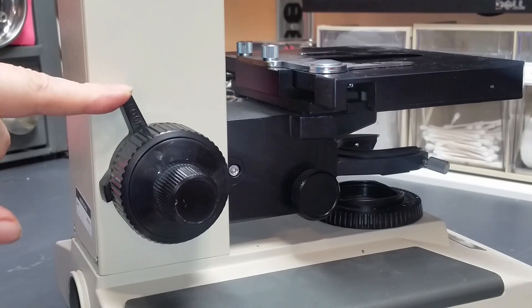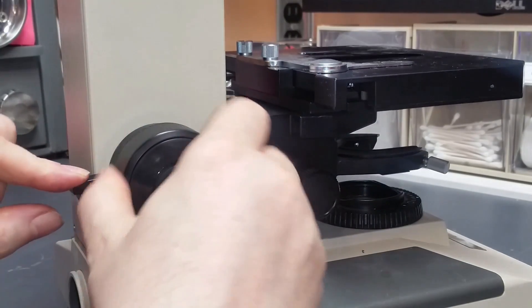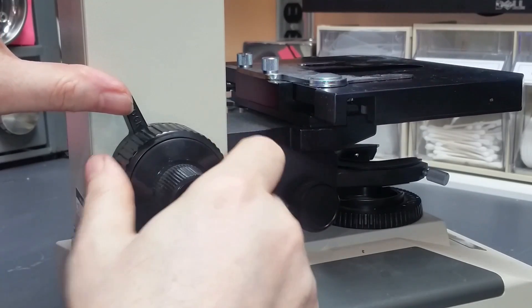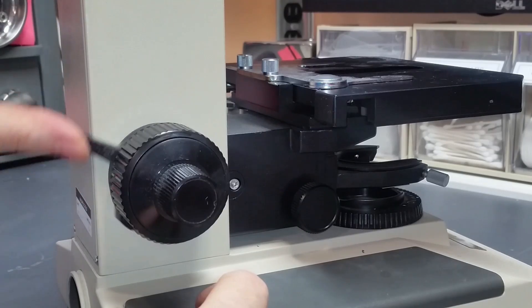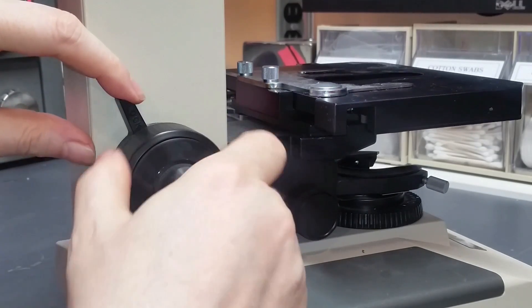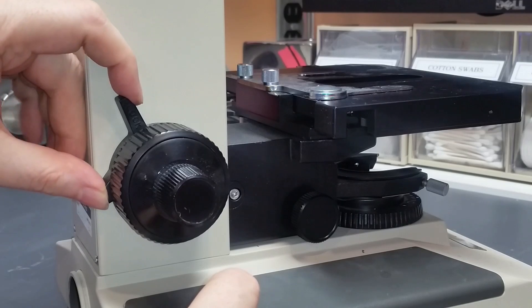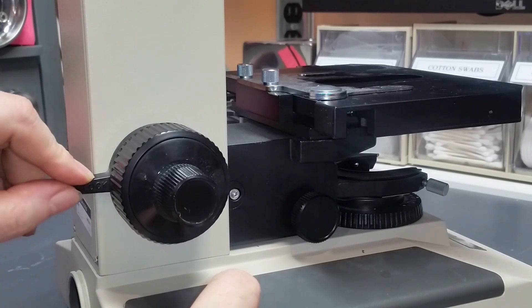Let's talk just a little bit about this. If you loosen this thing up, it's free to move up and down. Once you lock it, it won't go any higher — it will go down from that point. And if I release this, you'll hear that slap sound. That's characteristic of these things. If that slap sound is sluggish or muted, then that probably means you need to service this mechanism. But that's the basic mechanism of how it works.